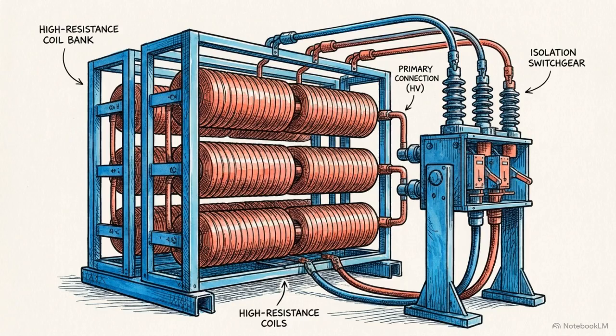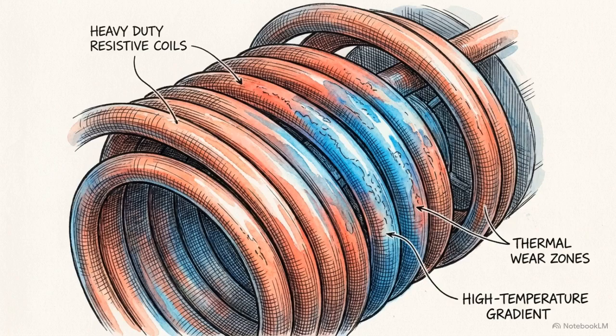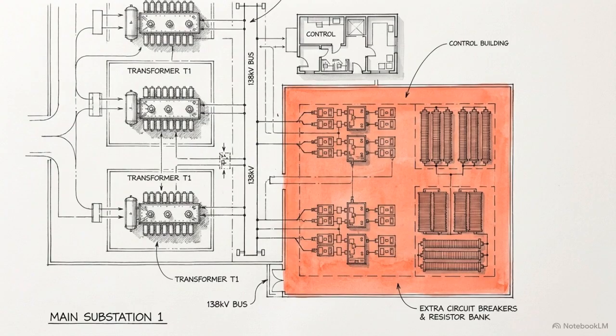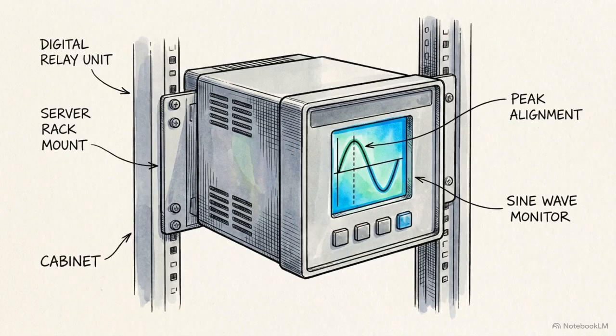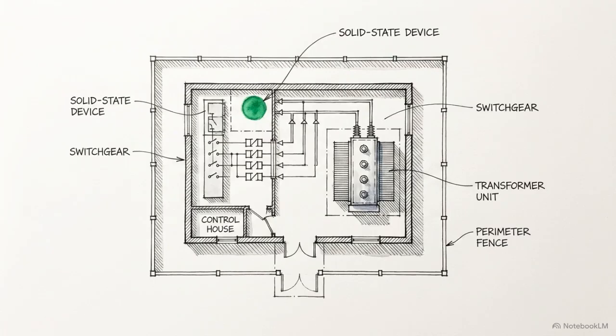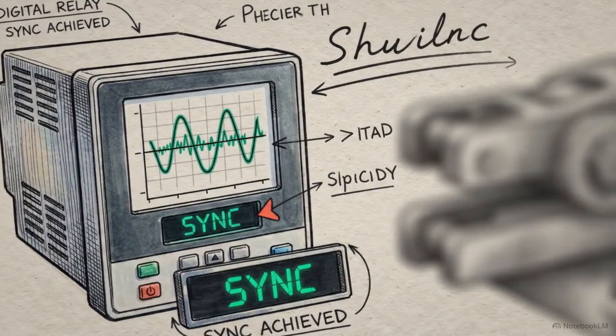The traditional mechanical alternative to this is the use of pre-insertion resistors. Pre-insertion resistors physically dampen the surge by placing resistance into the circuit for a few milliseconds. While effective, they require an extra circuit breaker, adding significant cost, mechanical complexity, and a much larger substation footprint. Point-on-wave relays, conversely, are compact, solid-state devices. They can be retrofitted or integrated directly into standard switchgear without expanding the physical site footprint. By digitally calculating the physics in real time, these technologies turn a probabilistic magnetic gamble into a highly repeatable engineered process.